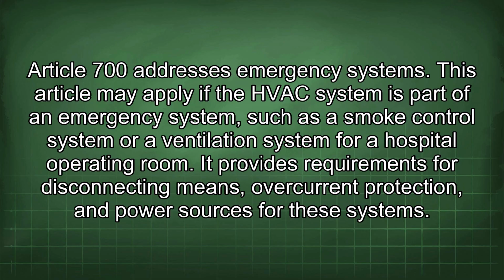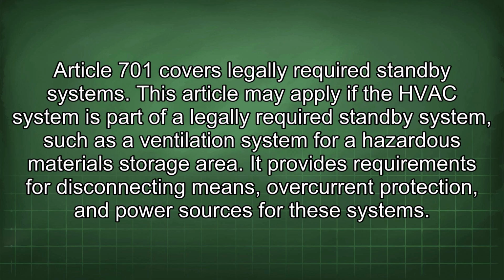Article 700 addresses emergency systems. This article may apply if the HVAC system is part of an emergency system, such as a smoke control system or a ventilation system for a hospital operating room. It provides requirements for disconnecting means, overcurrent protection, and power sources for these systems. Article 701 covers legally required standby systems. This article may apply if the HVAC system is part of a legally required standby system, such as a ventilation system for hazardous materials storage area. It provides requirements for disconnecting means, overcurrent protection, and power sources for these systems.